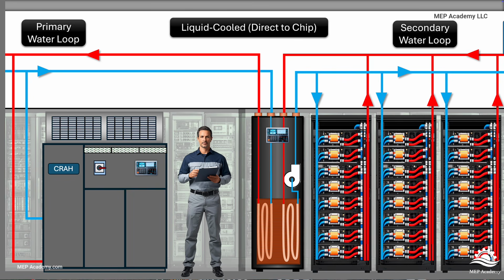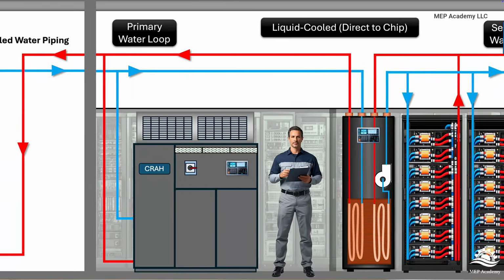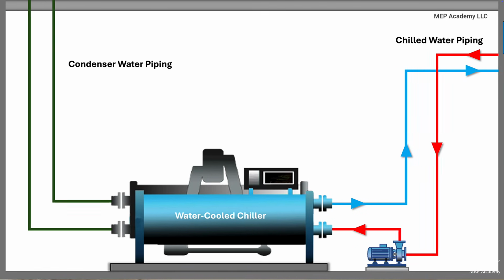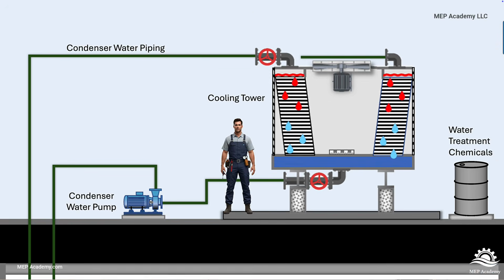Piping networks distribute coolant throughout the white space, much like chilled water systems distribute cooling throughout commercial buildings. In our example here, we have a chiller, serving both a chilled water CRAH unit and the cooling distribution unit. The heat is then rejected by the chiller through a condenser water loop served by a roof-mounted cooling tower.